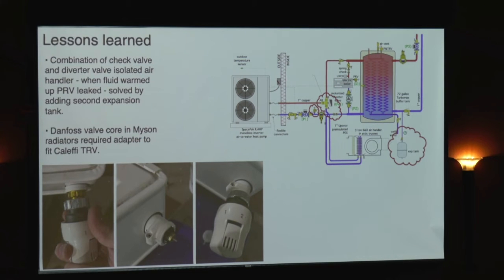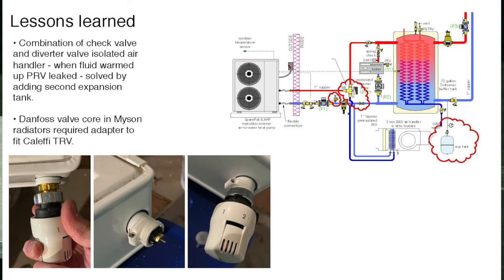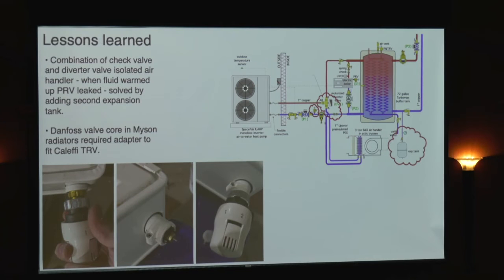Another lesson learned. I thought all these TRVs were kind of universal, that you could take anybody's TRV and screw it onto anybody's radiator valve. Not the case. The Myson radiators use a Danfoss valve core, and that valve core sticks out. And here's what happened. We took one, and the TRVs were by Caleffi. So I took one of the Caleffi TRVs and went to screw it on the radiator, and that's as far as I got, right there.